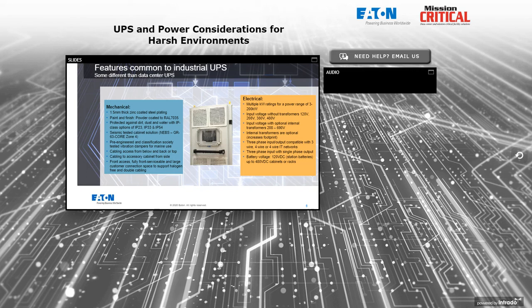But mechanically, we see things commonly like a thicker zinc-coated or corrosion-proof plating on the exterior and the interior surfaces of the machine. The paint and finish would typically be powder-coated or something even tougher than that. Typical paint processes for sheet metal would usually not be effective enough at eliminating the possibility of rust and corrosion. The air filtering in these machines needs to protect against dirt, dust, and water. IP 23, 33, and 54 are commonly requested capabilities for the enclosure for the machine. And sometimes that means that the UPS system gets placed in an exterior box with the appropriate filtering, doors and gasket seals, and the appropriate finish on the outside.